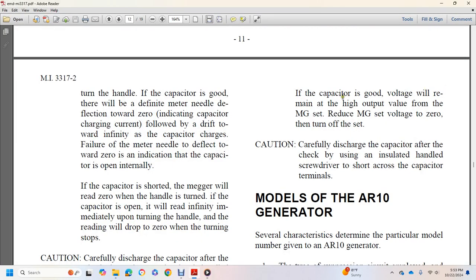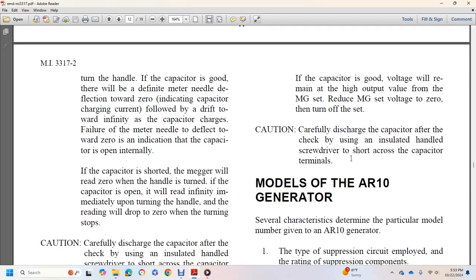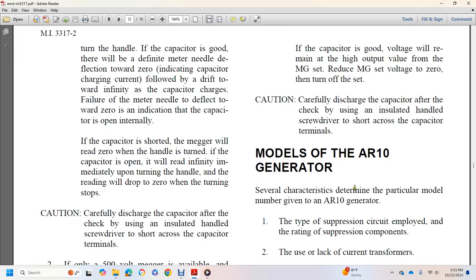If the capacitor is good, voltage will remain high at the output of the MG set. Reduce the MG set voltage to 0 and turn off the set. Carefully discharge the capacitor, then check with an insulated handled screwdriver, shorting across the capacitor terminals.